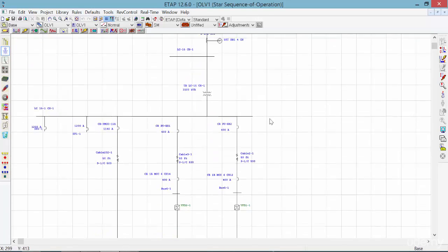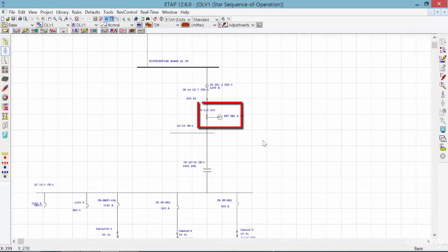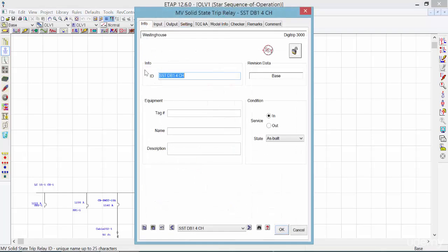And what we also have upstream here is a solid state trip relay which controls the upstream high voltage breaker, which I'm going to talk about, along with the current transformers, in my advanced ETAP course. But to give you quick information on what this solid state trip relay does: using the current transformer, it will detect the fault, and once it detects it, it's going to send a signal out to the upstream CBDB1 4CH1, and it's going to disconnect the line. And so now again, to get a quick idea about how this solid state trip relay works, let's double click on this relay and switch over to input.